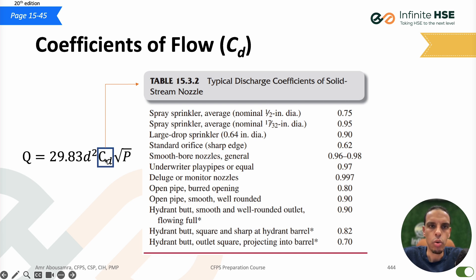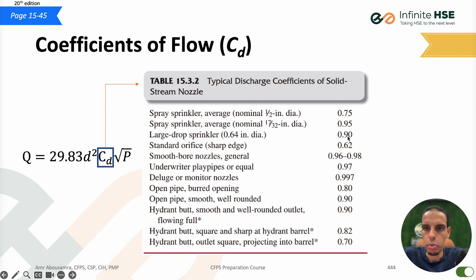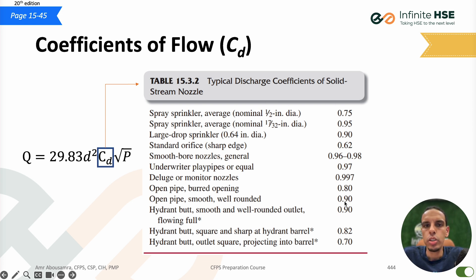The coefficient of flow, cd, is based on the material of the nozzle. For a normal spray sprinkler with a half-inch diameter, it is 0.75. The large drop sprinkler is 0.9. The deluge or monitor nozzle is 0.997. The open pipe with a smooth, well-rounded end is 0.9. This table of coefficient of flow values is important and you may be asked about it in the exam.